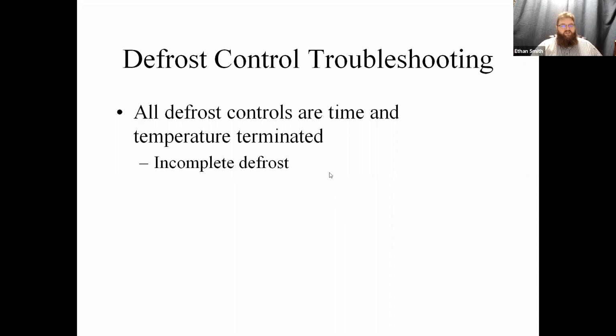Okay, so some of the symptoms we may see if our defrost control is not terminating properly or not working properly is an incomplete defrost. So we can have this if our sensors are causing that termination to activate too soon. That can be either a calibration issue where we have the wrong termination temperature set, or it could be that our thermistors are not reading properly.